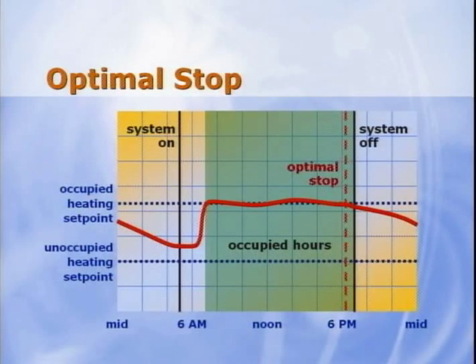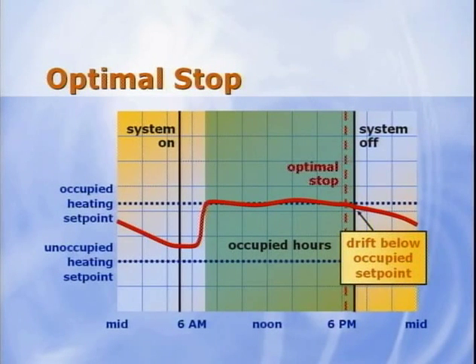A similar strategy is optimal stop. As I mentioned earlier, at the end of the occupied period, the system is shut off and the temperature is allowed to drift away from the occupied set point. However, the building occupants may not mind if the zone temperature drifts just a few degrees before they leave for the day. Optimal stop uses the same BAS to determine how early the heating and cooling can be shut off for a zone to allow the zone temperature to drift only a couple of degrees from the occupied set point. The supply fan continues to operate and the outdoor air damper remains open to continue ventilating the building. Only cooling and heating functions are terminated.